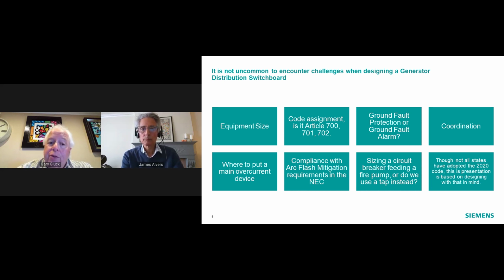Another issue that we run into is code assignment. Is the load 700 for emergency? Is it 701 for legally required? 702 optional standby? For those of you who are designing, we can kiss you when you put that information on the drawing associated with the breakers that it goes with. If not, put it with the transfer switch. We can figure it out.